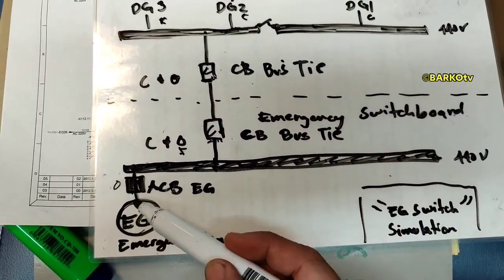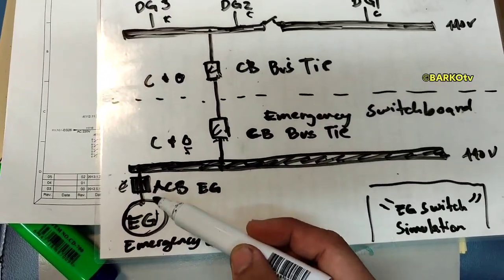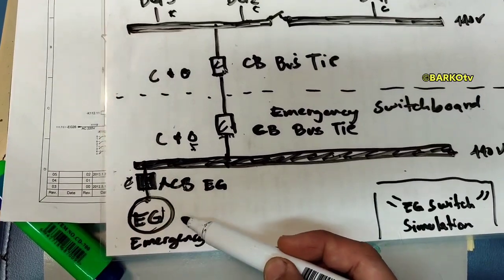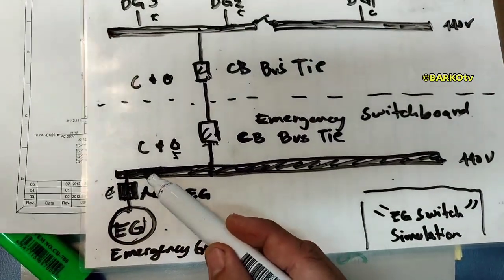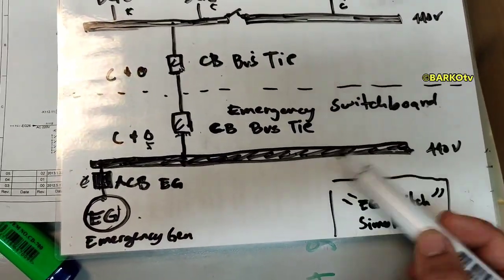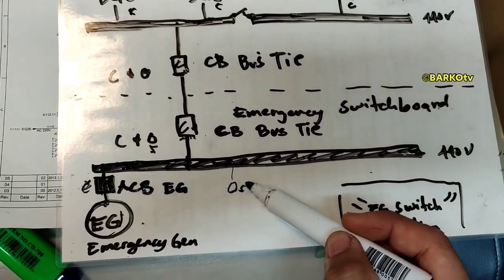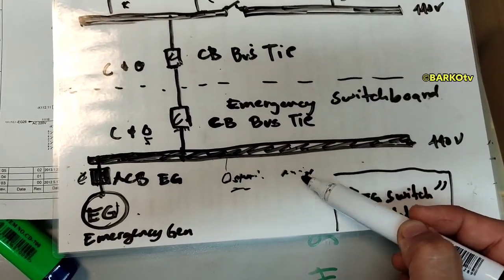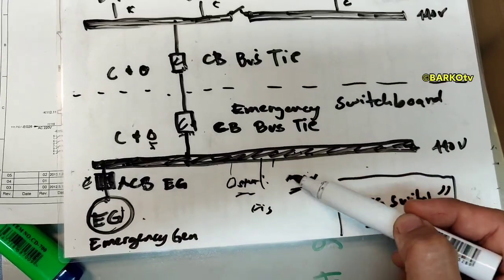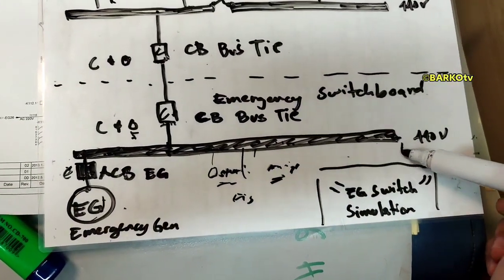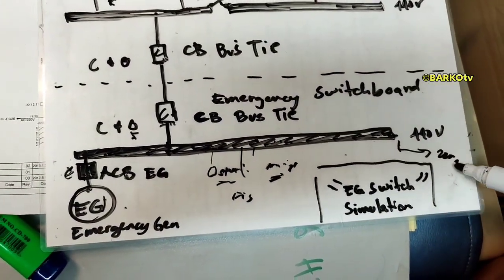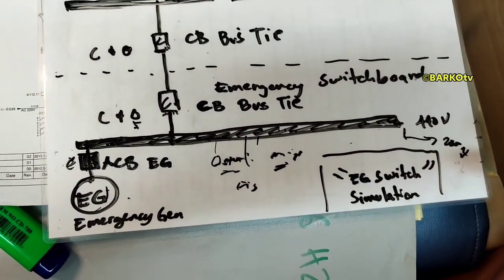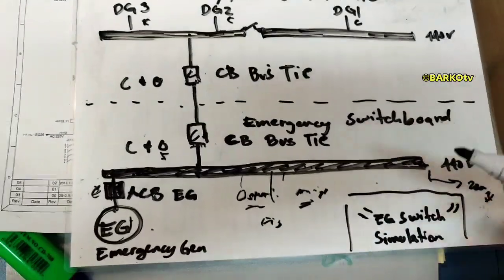After the isolation, the emergency generator will run, the ACB will close after the delay, and it will supply the emergency switchboard. The emergency switchboard powers important loads — for example, steering, main compressor number two, fire pumps, and also a transformer that converts voltage for emergency lighting and emergency power.